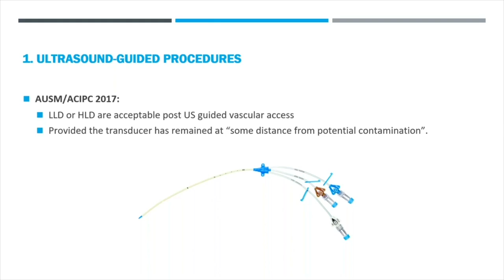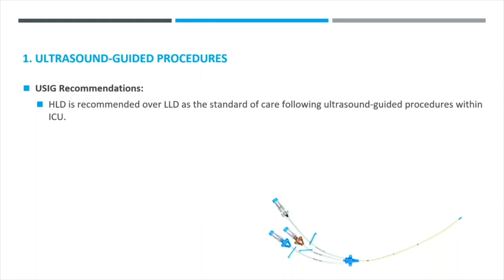Our recommendations are different. USIG is actually pushing much stronger and is strongly recommending high-level disinfection over low-level disinfection following vascular access use. And there were three reasons why we've come to this conclusion. First of all, at the end of the day, there are sharp needles being used, and the protection offered by sterile probe covers, in and of themselves, doesn't guarantee that they will not perforate, particularly in the context of needles being used in an emergency setting. So no matter what way you cut it, there is a risk of contamination that cannot be avoided.